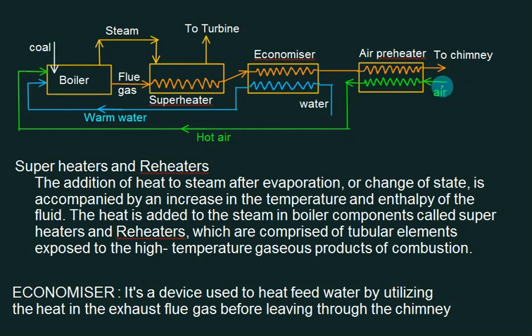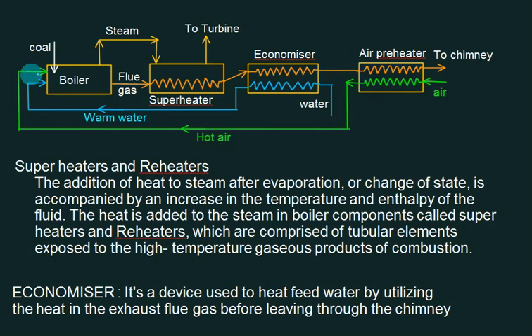Air is coming from the atmosphere and is slightly heated in the air preheater. From the other side, flue gases from the chimney are passing. Because of this, the temperature of air is slightly raised, and that hot air is supplied to the boiler. If the air is hot, naturally less heat is required to raise its temperature, so our heating is more effective.